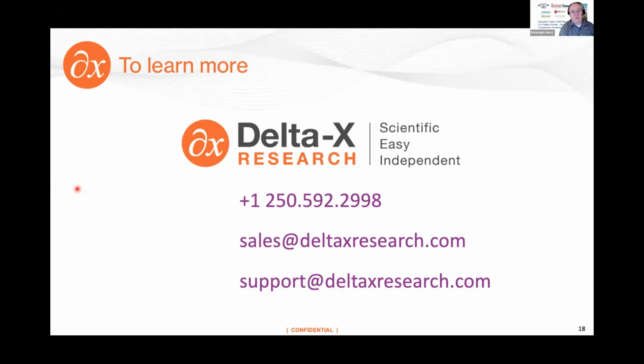What would you say the top 3 challenges are when it comes to DGA? Online monitoring? Okay, online monitoring top 3. The reliability of the sensors has been a big issue. Technology is improving, but it's fairly expensive. We're seeing some improvements in technology, but the simpler you can keep it, the better. If you can get away with a smaller, simpler monitor, then you might be better off from a reliability perspective.